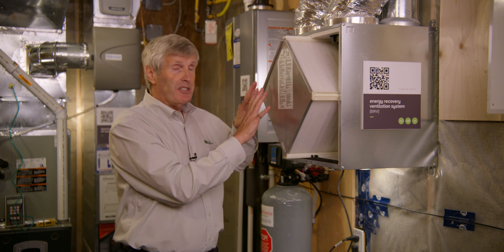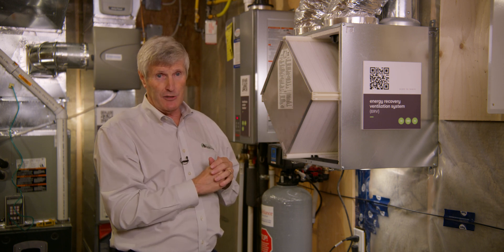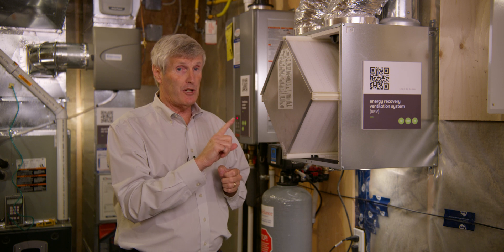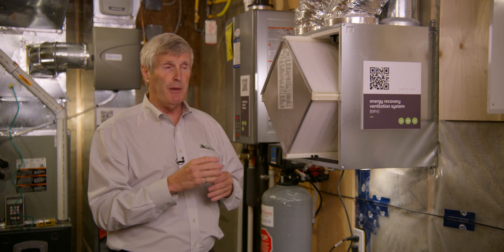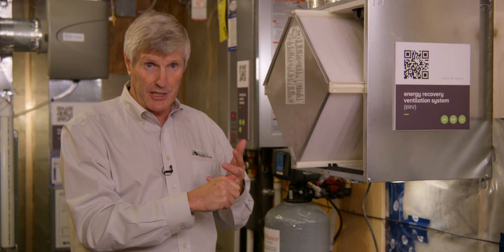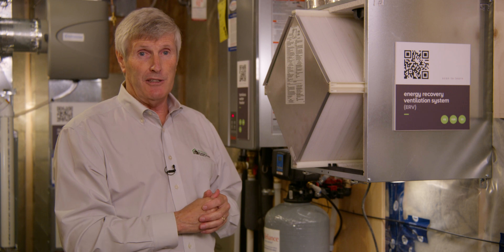The technology we feel best about in today's world for the vast majority of Canadian houses is the energy recovery ventilator — remember, whole house fresh air — with the ability to remove or reject 50 to 70% of the moisture in that airstream. What a win-win: fresh air for occupants, better moisture control in houses, and tremendous energy efficiency, which is frankly part of all new houses in Canada these days.